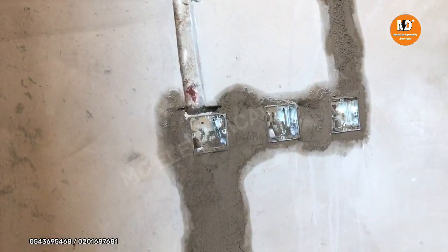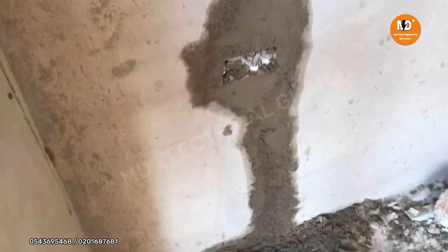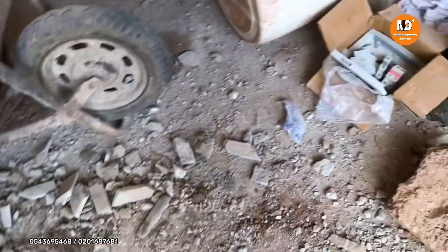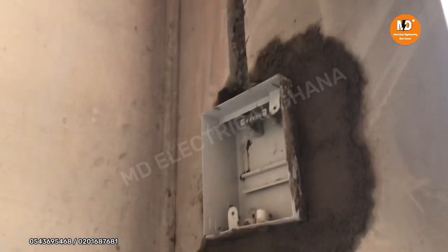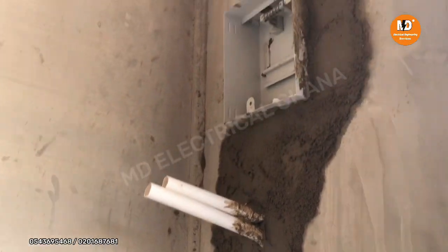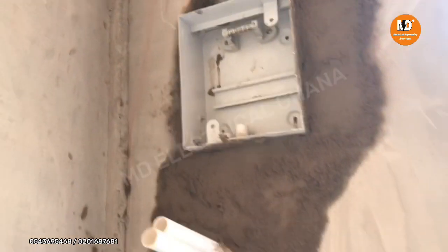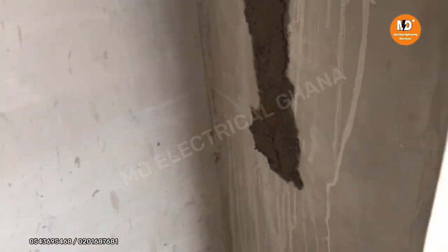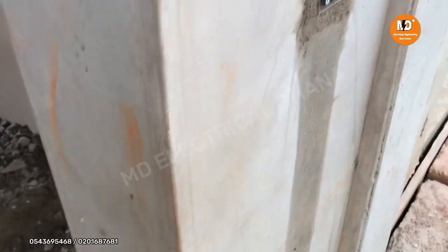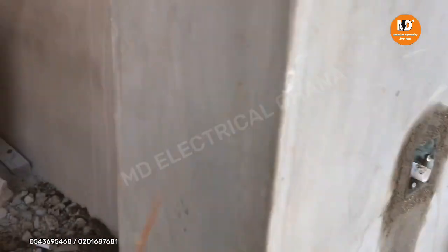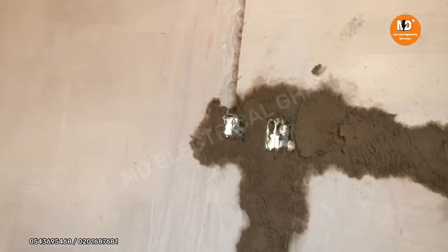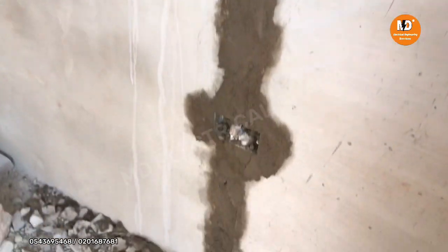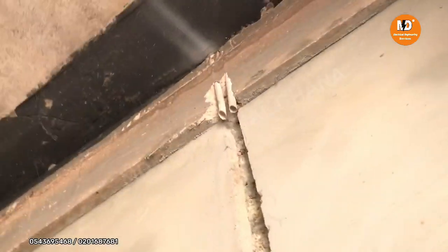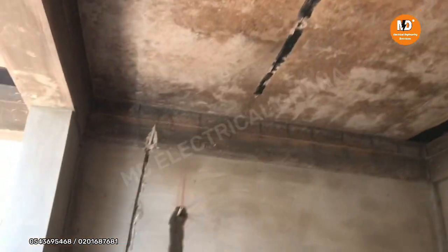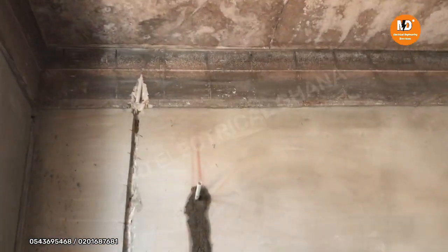Okay, so meaning AC goes for one breaker, the lighting system goes for a separate breaker, and the socket system too. Yes, so we don't want to put much load on the breakers. Yes, we want everything to be well balanced. So that's the reason why we went in for a four-way distribution board.